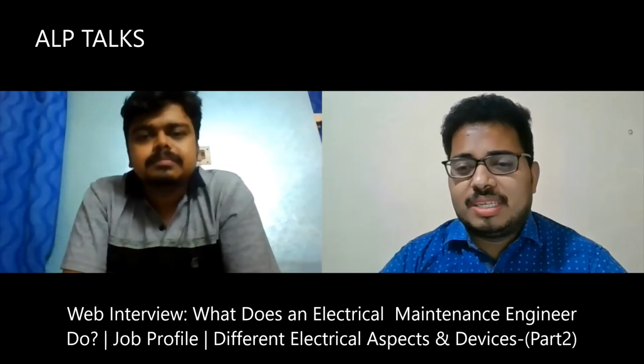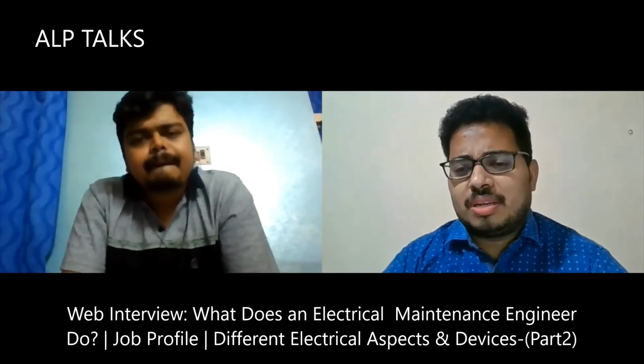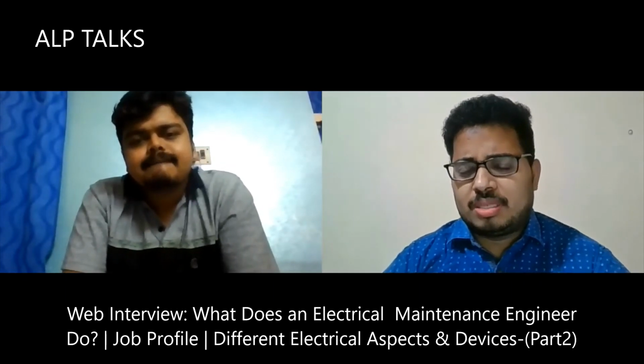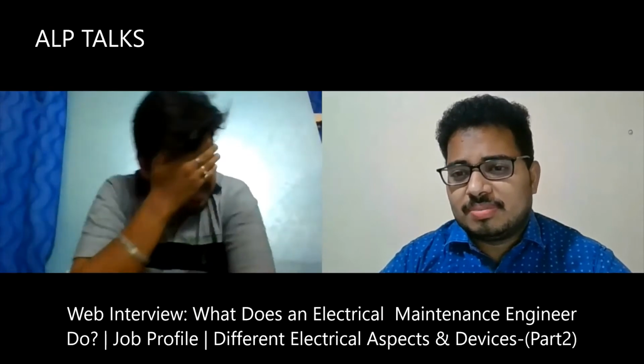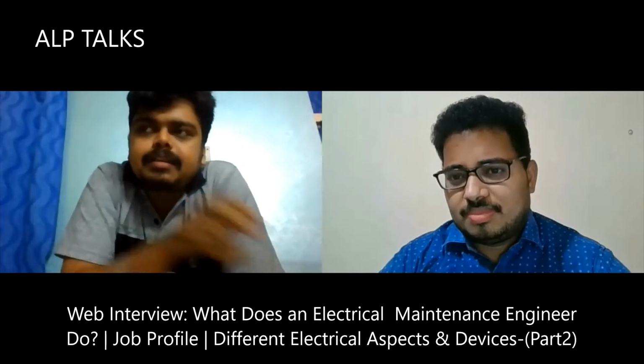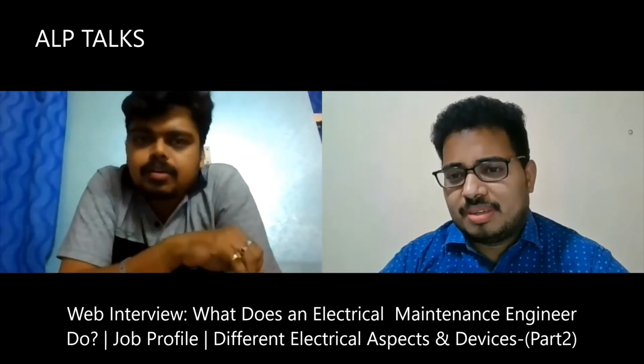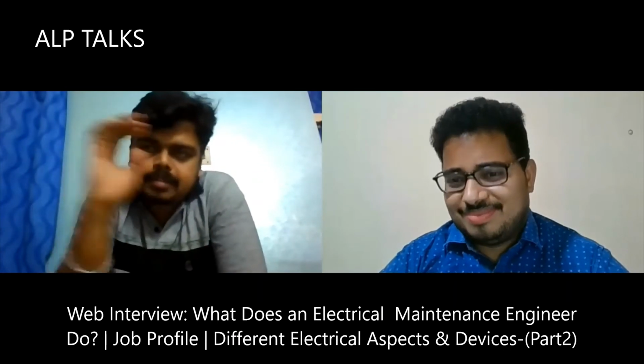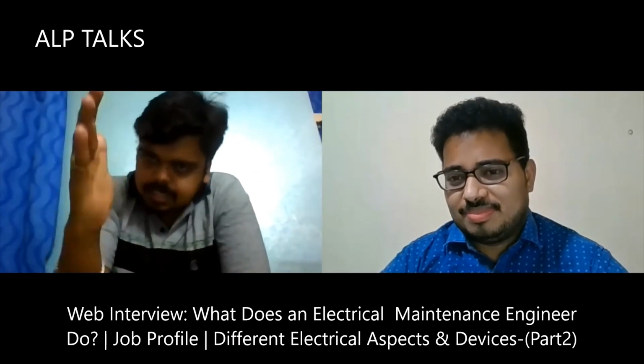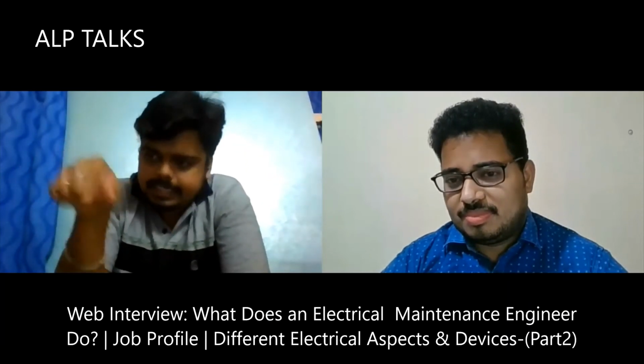So generally where do they use ACB and where do they use VCB in a substation? In 6.6 kV incoming, VCB is there, and after VCB it goes to the transformer. But in ACB, at the 440 volt incoming incomer busbar, before going to any motor you have to use ACB, then VFD, and through the VFD it goes to the load. This is the main setup.